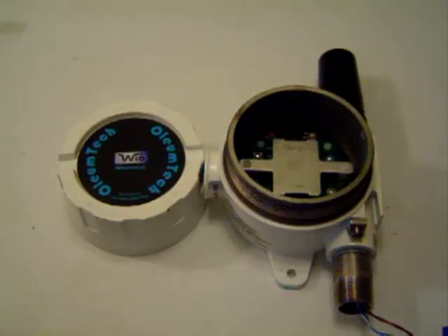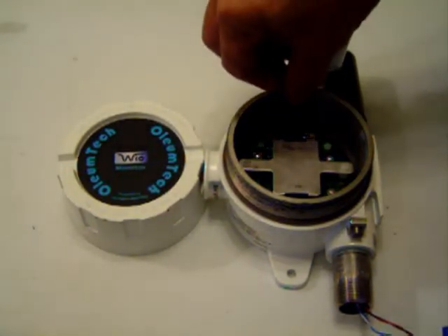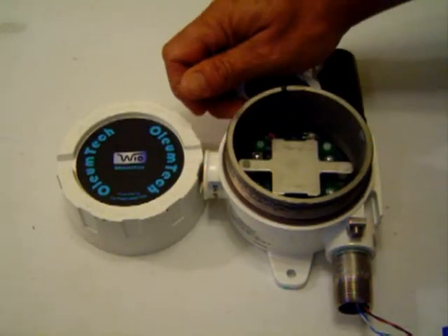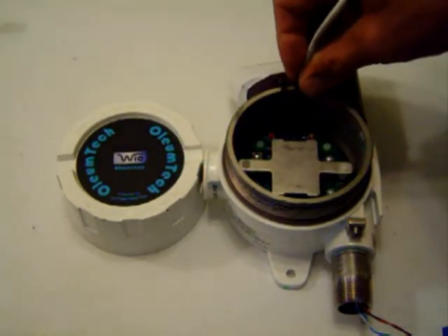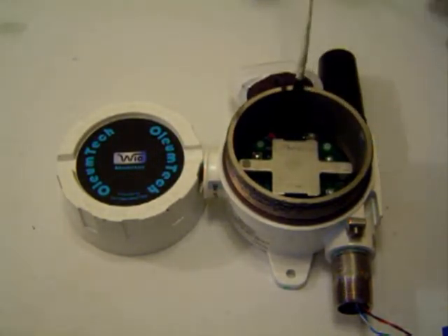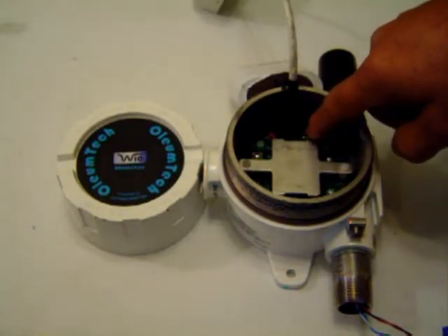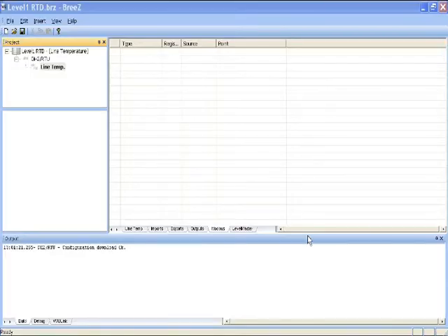Transmitter connections include a 3-pin flat for battery connection, a 4-pin flat for Breeze configuration connection, and the reset switch is located right beside both connections. Now you can remove your configuration cable from the DH2. Install your configuration pigtail for the transmitter. Then plug the 4-pin flat into the transmitter.